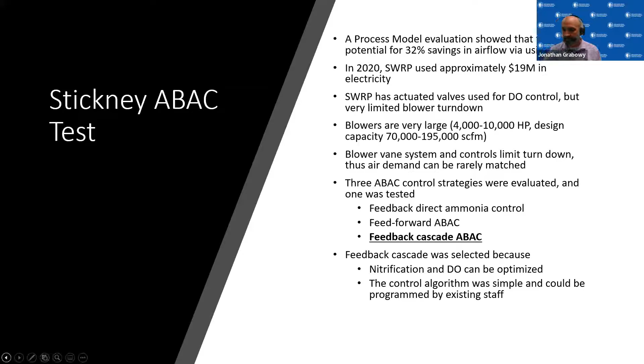We looked at a bunch of different methodologies. We looked at feedback directed ammonia control, feed forward ammonia-based aeration control, and feedback cascade ammonia-based aeration control. We selected the feedback cascade method because the nitrification and the DO could be optimized, and it was a simple enough process for us to do internally with internal staff and with our existing resources. If you could go to the next slide.